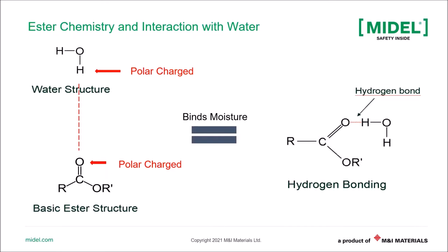And the basic ester structure has this polar charge I just pointed out to you. What this means is that you get hydrogen bonding. You get this magnetic attraction to water where you bind it up and you don't release it. And this is particularly important in a transformer environment where water is a breakdown product from the cellulose aging. And if any water ingresses to the system, you will be able to bind it up with ester chemistry, that is. This means it won't separate, it won't gas, it won't form a separate layer like it would with mineral oil. And so this property of esters is really what drives the extended life and performance of esters as transformer liquids.